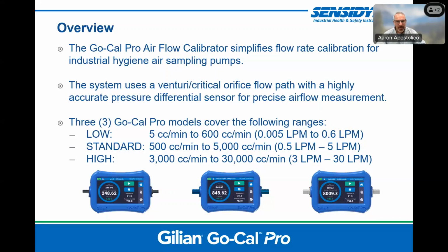Now we have 3 different flow models. We have a low flow model, which ranges from 5 cc's all the way up to 600 cc's, predominantly used for your sorbent tube and gases and vapor states. You have your standard flow range, which goes from 500 cc's all the way up to 5 liters per minute. And then you have your high flow, which ranges from 3,000 cc's all the way up to 30,000 cc's or 30 liters per minute.